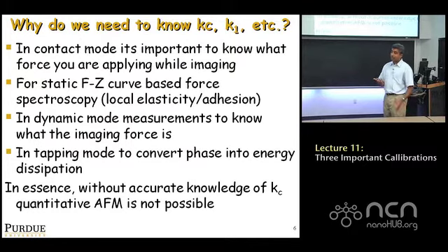In fact, if you think about it, with 100 nanonewtons of force, the tip radius is typically 10 nanometers. You apply 100 nanonewtons over a circular area of 10 nanometers, and you calculate the stress you're creating. It is more than the yield stress of most materials. You're applying a small force, but on an even smaller area, so the stresses are huge. Normal stresses are huge, right? You easily reach a gigapascal with 100 nanonewtons of force underneath. So this is a problem.